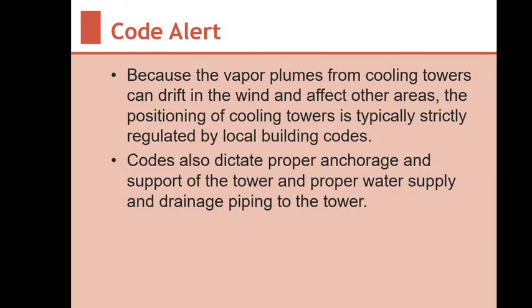Here's a code alert. Because the vapor fumes from a cooling tower can drift into the wind and affect other areas, the positioning of cooling towers is typically strictly regulated by local building codes. Codes also dictate proper anchorage and support of the towers and proper water supply and drain piping to the tower.